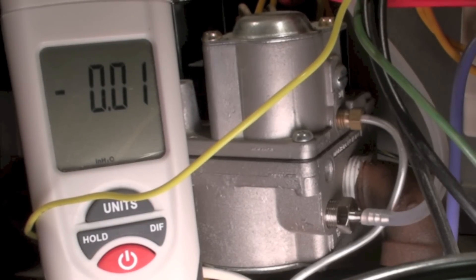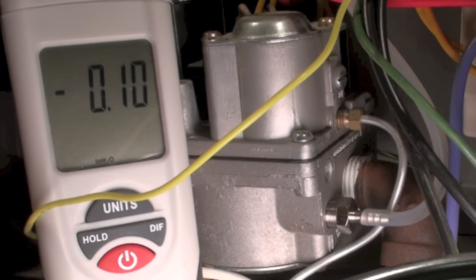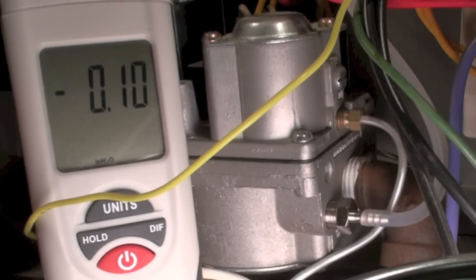Okay, we've got the manometer on it. I'm going to start up the forced draft blower. Now that's already put one-tenth of an inch water column on this thing. Reason is I pressurized the combustion chamber. Remember, this is a positive pressure combustion chamber.